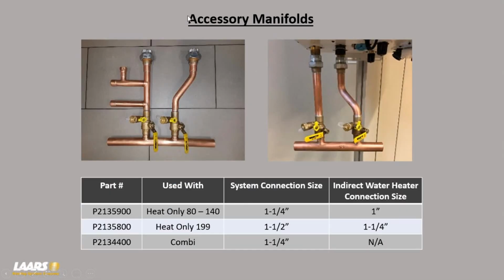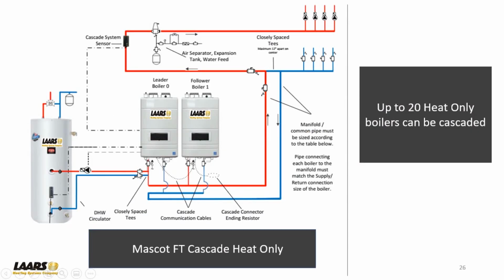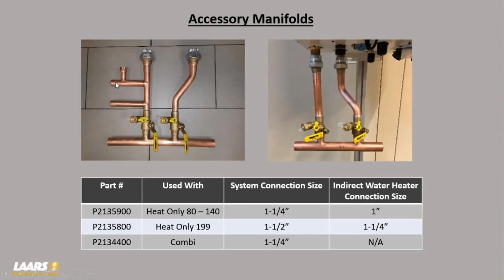Now we offer these manifolds, these accessories, and here are your part numbers. Here on the left-hand side is the heating only model. And I talked about 2 stub outs. Here's your stub outs for your indirect. They're capped, just uncap them. But this little port here is for your relief valve for a heating only model. So primary, secondaries right here. You already got your 2 closely spaced T's, ball valve, you can purge your system. So these manifold accessories are all set for you if you care to purchase them, or you can just plumb in primary, secondary yourself. On the right-hand side is the Combi, okay?